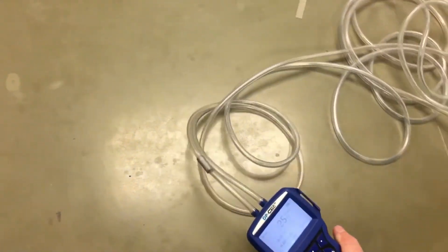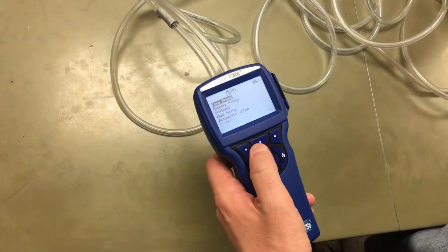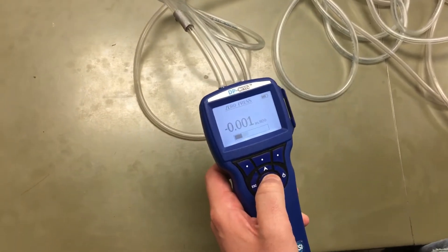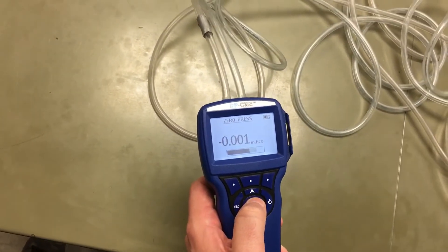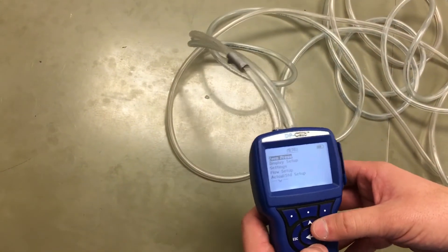Before we take our measurements, we need to make sure it's set up right, so we're going to go to the menu and zero the pressure. This sets the pressure of the ambient air that it's taking in right now as the zero point for our measurements.